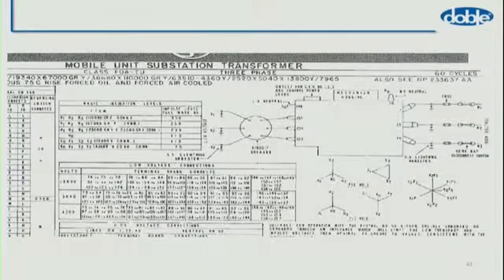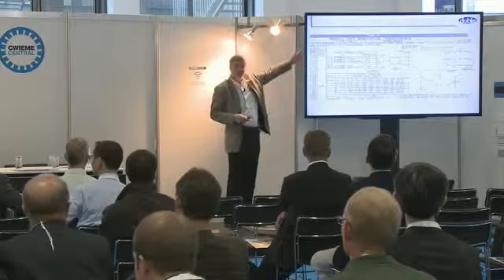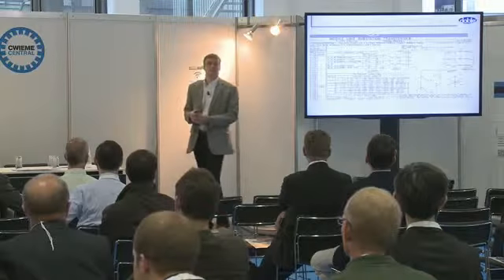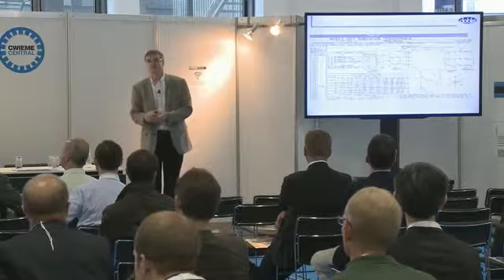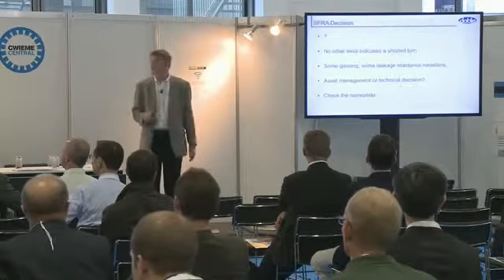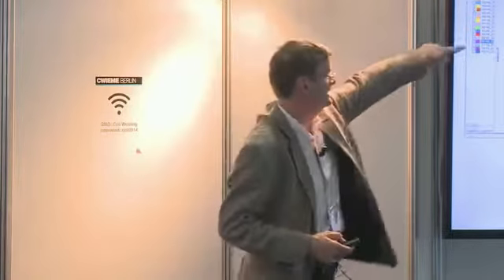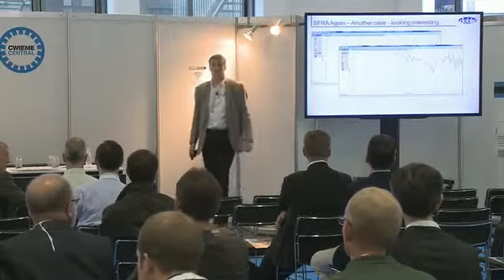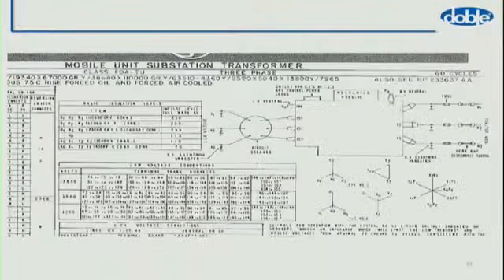No other test really showed that. And when you look at the nameplate, there's enough information there to allow you to make an actionable conclusion. And the conclusion is it goes back in service. And the reason for that is during testing, someone's identified a tertiary winding. Can anyone see the tertiary winding on that transformer? It's not obvious.